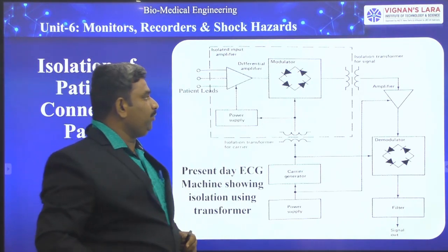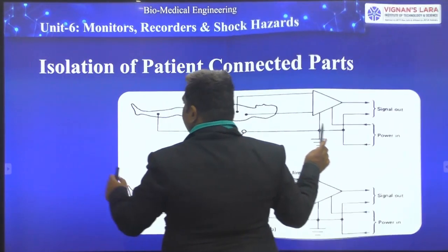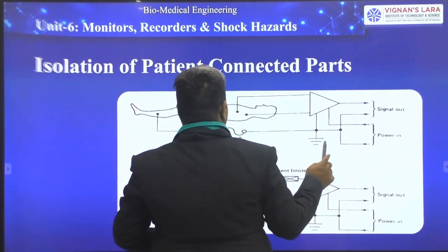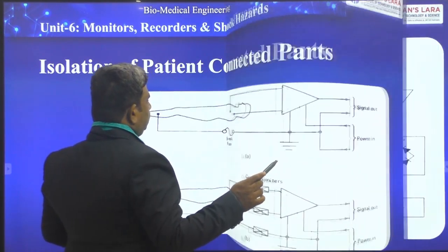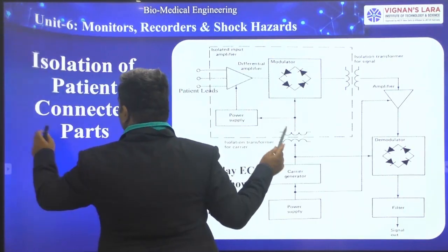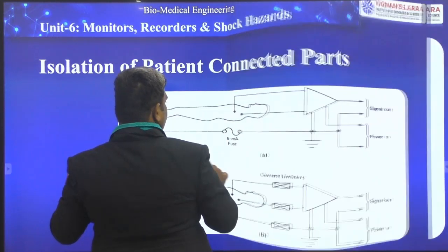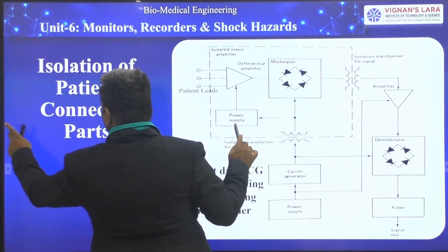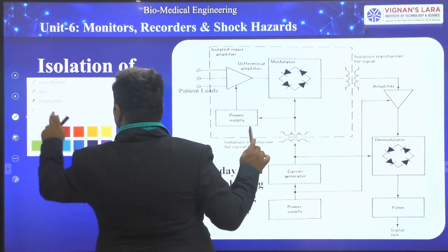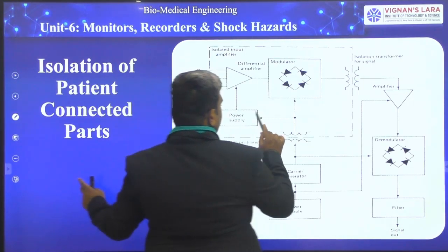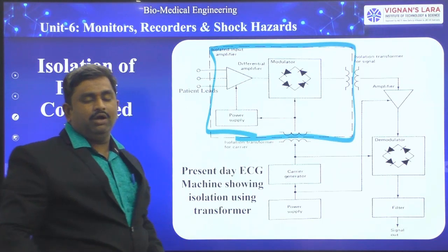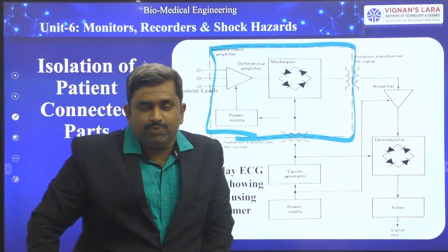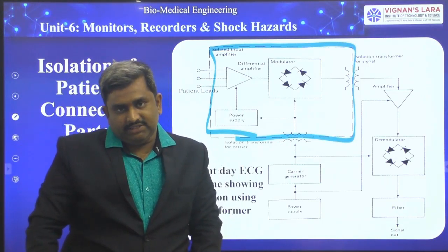These patient connected wires we are keeping in a separate box, which is protected by the isolation transformer.